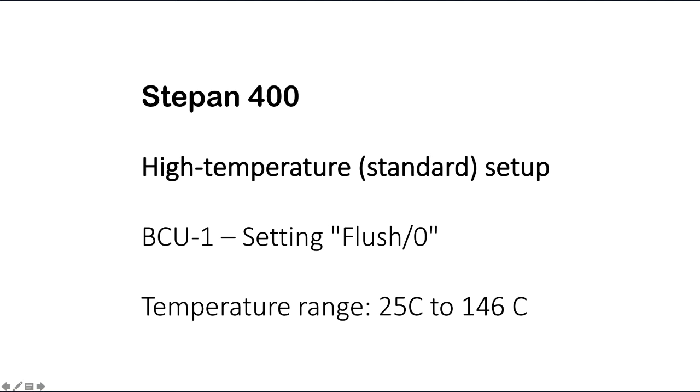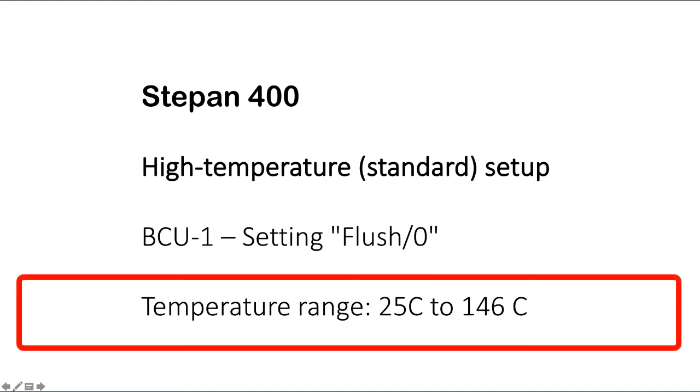This tutorial covers standard setup on 400 in Stepan. The instrument operates at ambient temperature and all the way up to 146 degrees C, which is the last calibrated point.